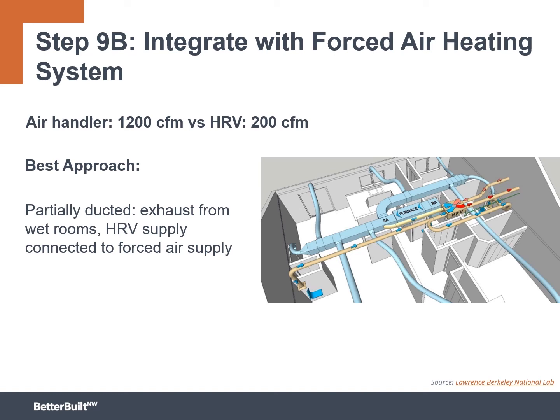So the best approach to do this, we call it a partially ducted system. We fully duct all of the exhaust out of all the bathrooms, utility rooms, and laundry rooms that we talked about earlier. But then we take the HRV supply and we connect it to the forced air central system's supply duct. And in just a second, we're going to go into a little bit more detail on this.